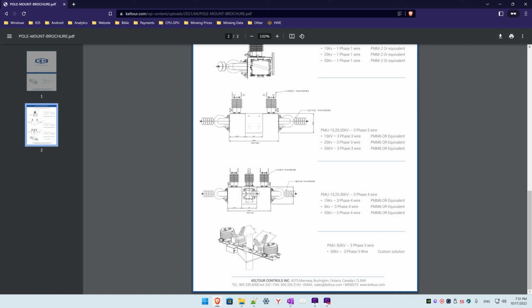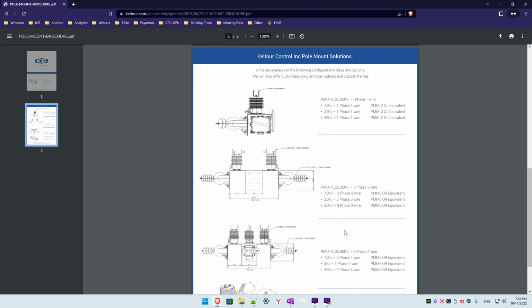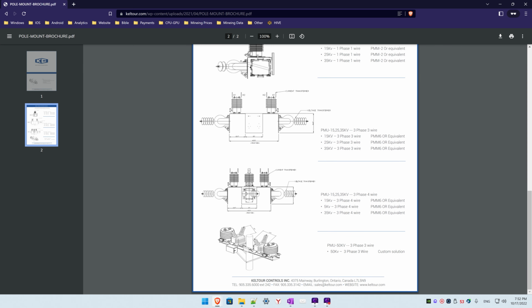In our situation, we're getting one transformer at 2.2, so 2,200 kVA, running two containers at 1 megawatt each, and a third container at about 200,000 watts. We'll have leftover with the GPU. Our client here is going to be moving a lot of his GPUs from one of the places we're renting out into this property. Those 200,000 watts left over from the 2.2, we're going to use to power the GPUs, and then use 1 megawatt to power one container and another megawatt to power the second container.